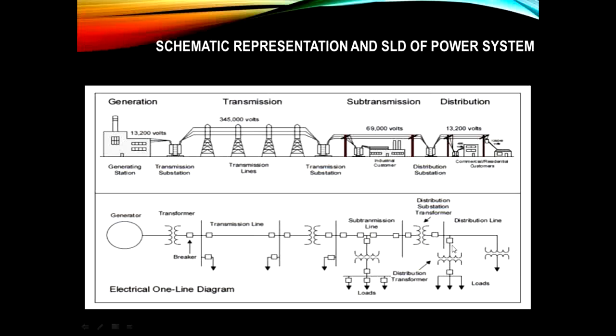That power comes to the transformer near your home, where it is converted into 415 volts. The primary side may be 11 kV or 33 kV, and the secondary side will be 415 volts, having 3 lines R, Y, B with neutral. If you take voltage between two phases, R and Y, you should get 415 volts. If you take phase and neutral, you get 230 volts, which is what you need for your supply.